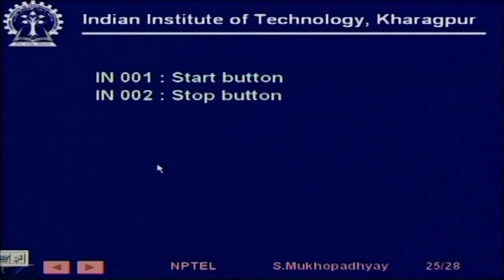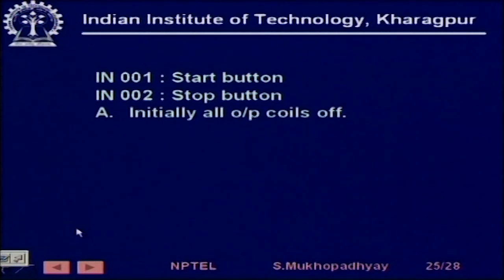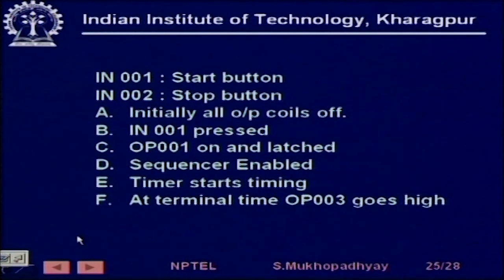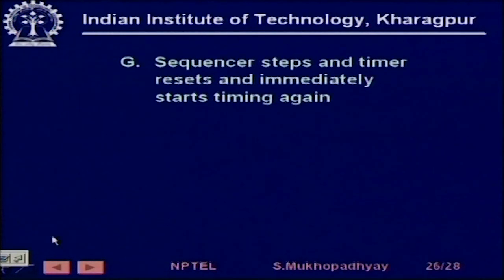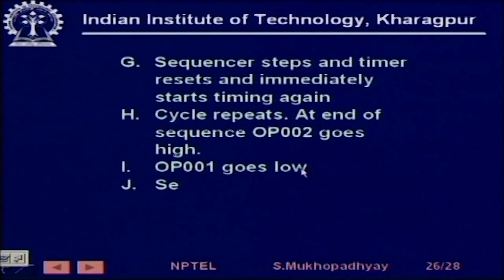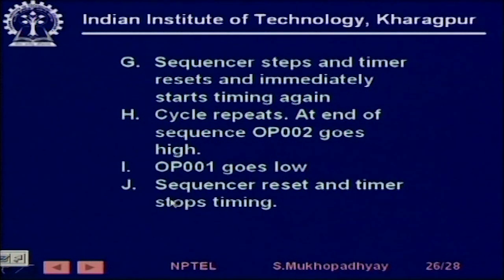To summarize: IN001 is a start button, IN002 is a stop button. Initially all output coils are off. When IN001 is pressed, output 001 goes on and is latched, then the sequencer is enabled and the timer starts timing. At terminal time, output 003 goes high, the sequencer steps, and the timer resets and immediately starts timing again. This cycle repeats. At the end of the sequence, OP002 goes high, OP001 goes low, and the sequencer resets and the timer stops timing.